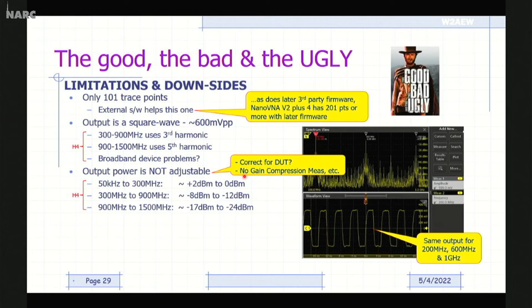Also, the receive level into port 2, or channel 1, of the Nano VNA is not adjustable. So if you're measuring an amplifier that's got 20 dB of gain, you might need to attenuate that back down so you don't overdrive the input of the Nano VNA. And they generally have a limited dynamic range compared to the professional units. The H and H4 are in the neighborhood of 40 to 45 dB dynamic range. At lower frequencies, a little bit better; at higher frequencies, a little bit worse. The V2s are better, getting up to closer to 60 or 70 dB dynamic range, or a little bit better.